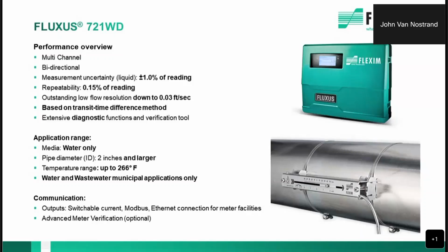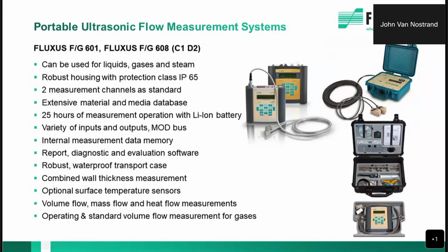So the 721 meter is suitable for water and wastewater applications, and it's available with multiple transducers, like I said, for pipe diameters above 2 inches. We have another meter that we can measure down to a half an inch, which we do often when it comes to chemical dosing and so on. Chemical dosing is really important in the water market. We know this, and because we're actually measuring about 8 times per second, we can handle the pulsations. So not to worry if you have a pulsating pump or peristaltic pump or a diaphragm metering pump or something like that. We can still measure your polymers and your hypochlorite and so on.